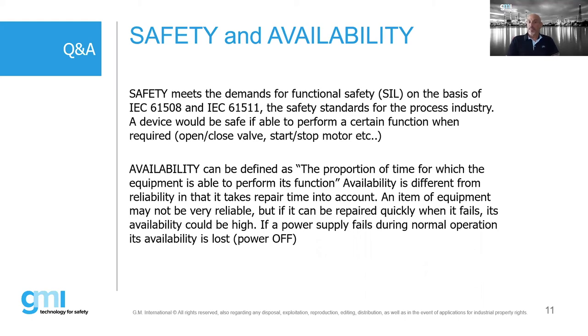But availability is also very, very important. It is defined as the proportion of time for which the equipment is able to perform its function. So availability is different from reliability. It means that a device is available for most of the time that I need. If the power supply fails during normal operation, its availability is lost. If it fails and my system goes off because of the failure, that is a fail safe. My plant is not working. I'm in a safe position, but I'm not operating, so I'm not available. I cannot produce. That is very, very important.